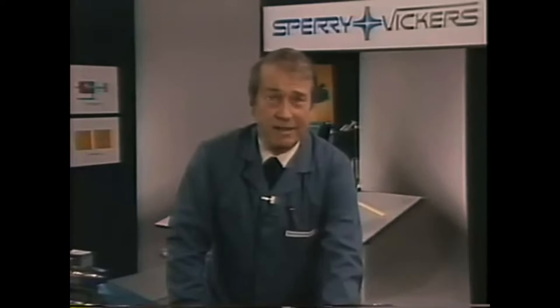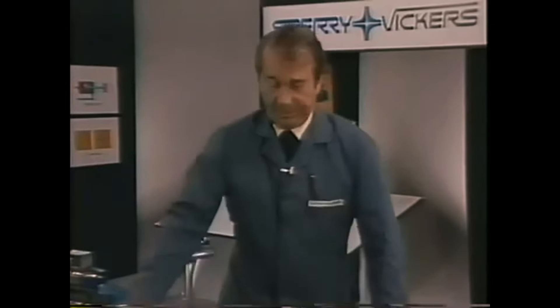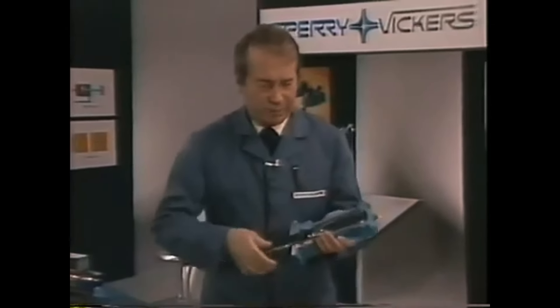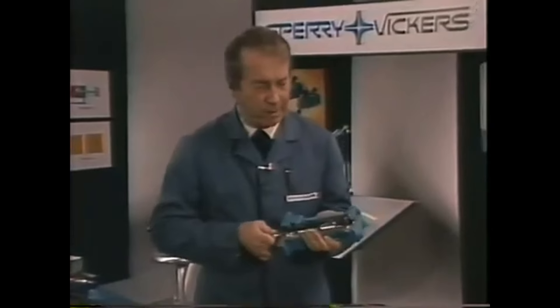Basically, there are two motions we can achieve hydraulically. We can move something in a straight line, or we can make something rotate. A cylinder, or linear actuator, provides the straight line motion. It can be single-acting, like a hydraulic jack, where the weight of the car brings it back down, or double-acting, where the piston is forced both forward and backward in its bore, by fluid under pressure.